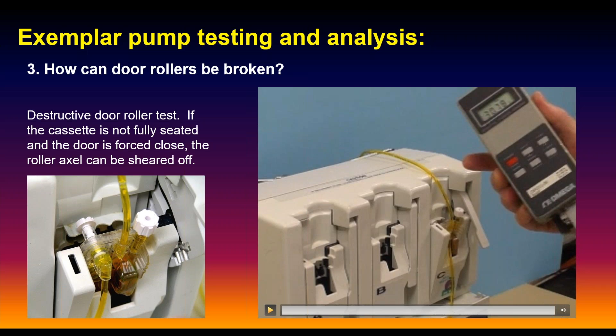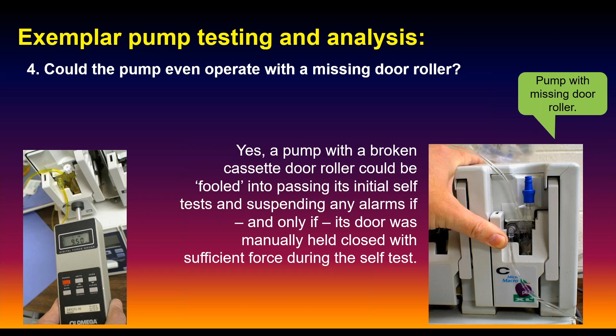Okay, so fundamentally, what I ended up finding out, though, was that even with the door broken, and this was just pure accident, if I held the door closed with just the right amount of force for just the right amount of time, so if I had 3 to 7 pounds of force, if it was less than 3, I get an alarm. If it was more than 7, I get an alarm. And I had to keep it closed for just a few seconds while the pump ran through its self-test. The pump would start and run with a broken door roller. It would actually run, but you had to go through that precise and exact scenario in order to make that happen. And the point I made is, how likely is that?